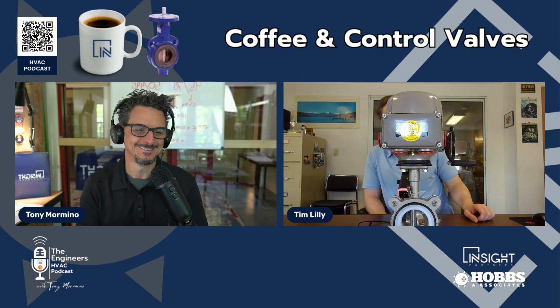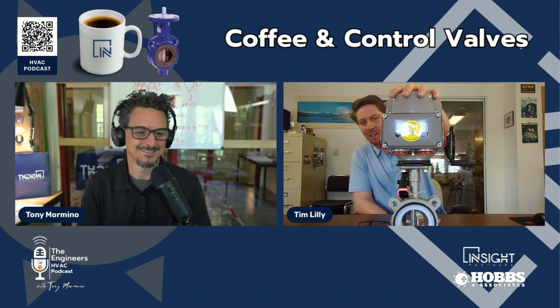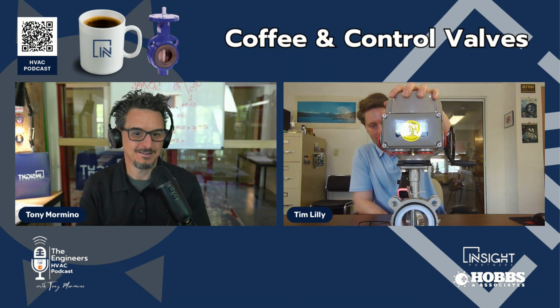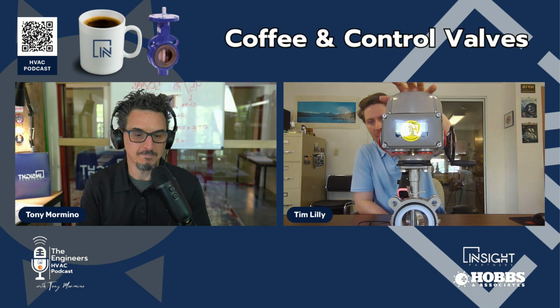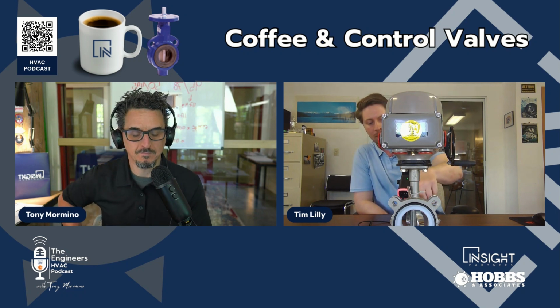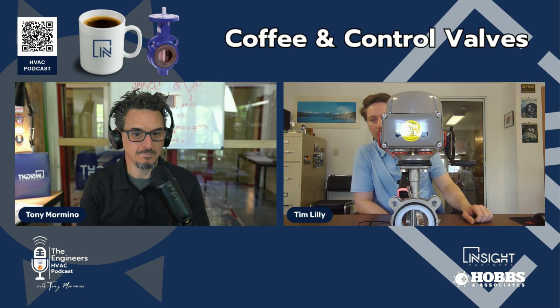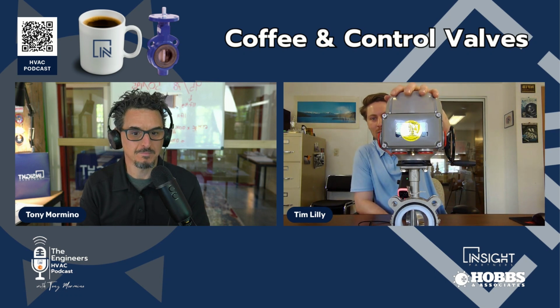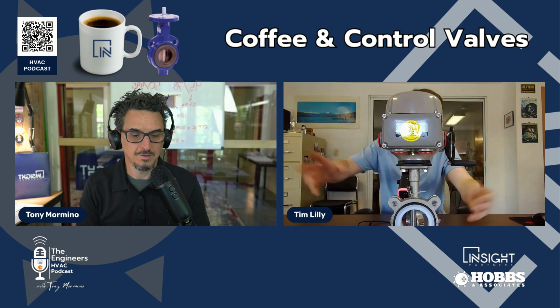So it's great. And then this is an electric actuator. It's very simple. You just run a wire or two to this, and then you give it a signal on a 0 to 10 scale, and then it'll move your disc and it'll modulate your flow. It'll go open, it'll go closed, and you can sit in your control room and set your program, send your signal through the wiring. You can run an entire steel mill with 2 wires, which is incredible. Whoever figured that out is incredible. And you can do the same thing in the HVAC world, and they do it in the HVAC world.